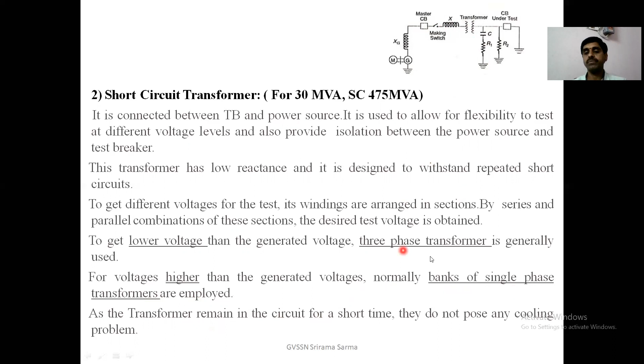To get different voltages for the test, its windings are arranged in sections. By series and parallel combination of these sections, the desired test voltage is obtained. To get a lower voltage than the generated voltage, a three-phase transformer is generally used. For voltages higher than the generated voltage, banks of single-phase transformers are normally employed. As the transformer remains in the circuit for a very short time, because the testing procedure is very short, they do not need any cooling mechanism. So cooling is not a big issue here.